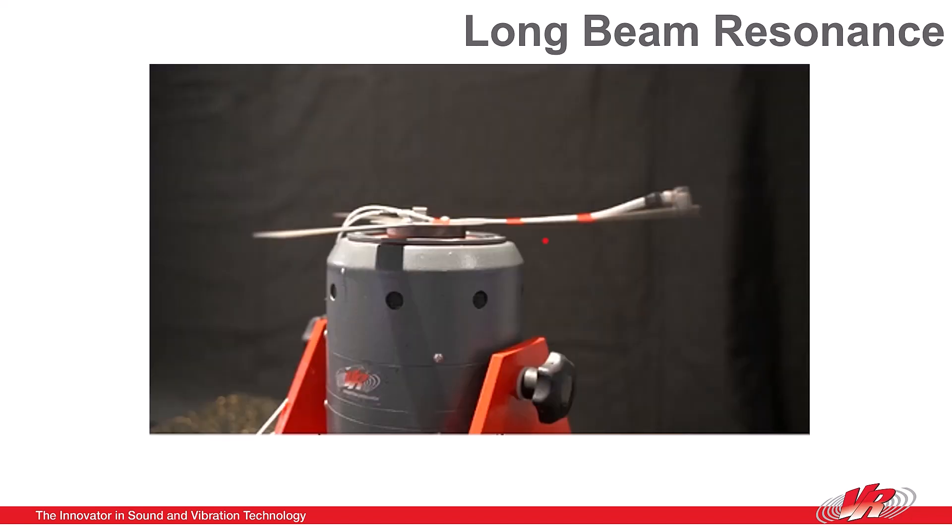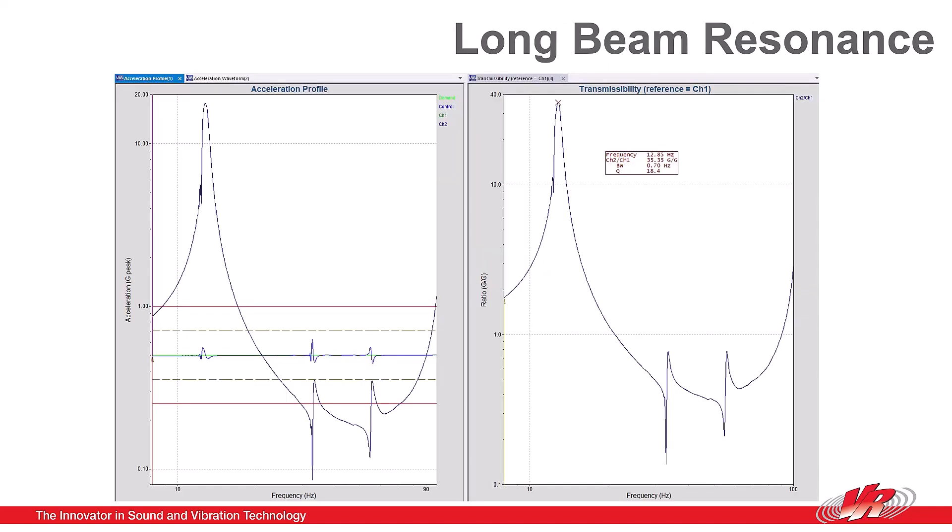In a previous test with our fixture of three different length beams, the accelerometer used was relatively large and had significant mass loading effects. On the first test, the accelerometer was mounted to the end of the longest beam. You can see on the VibrationVIEW software that the accelerometer showed a large resonance at about 12.5 Hz.